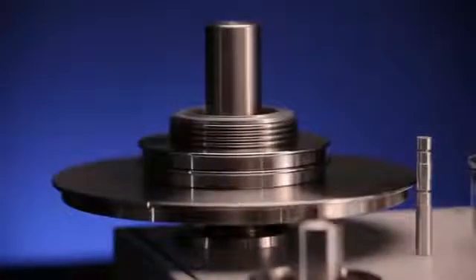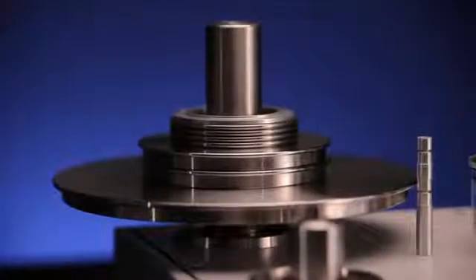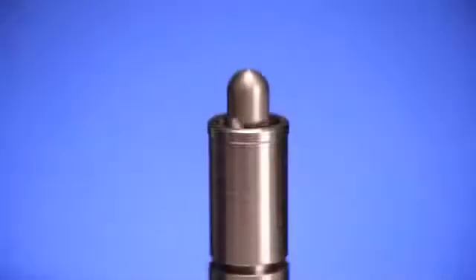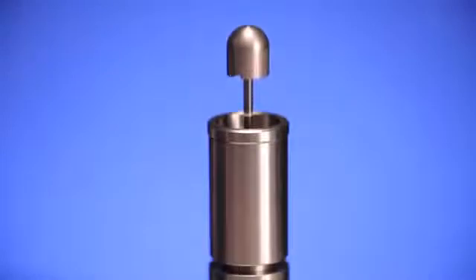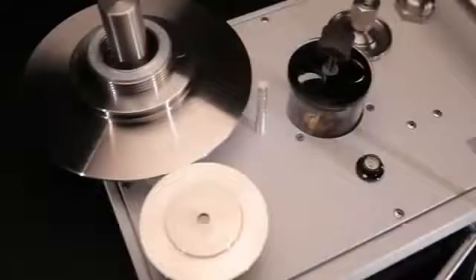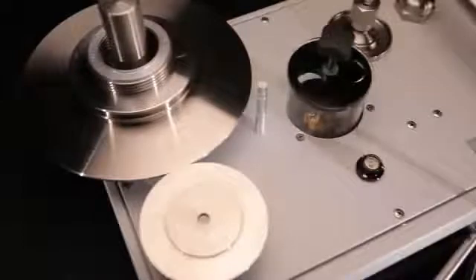The pistons are made from tungsten carbide to ensure good long-term stability. The fit between the piston cylinder is built to exacting tolerances. The weights are made from non-magnetic stainless steel or aluminum to ensure that magnetic forces do not interfere with the calibration.